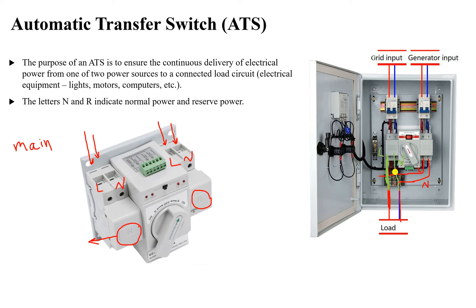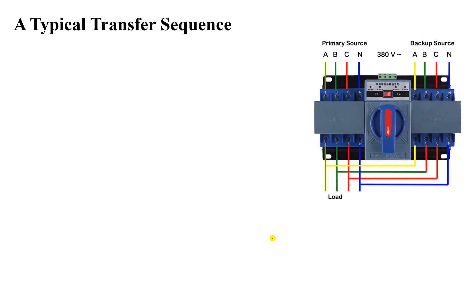The automatic transfer switch operates only one of these sources at a time — electrical power can come from the primary source or from the backup source, but not both simultaneously. For a three-phase automatic transfer switch, N is the normal power and R is the reserve power. The primary source is three-phase plus neutral, and the outputs are connected in parallel — line A to A, B to B, C to C, and neutral to neutral.